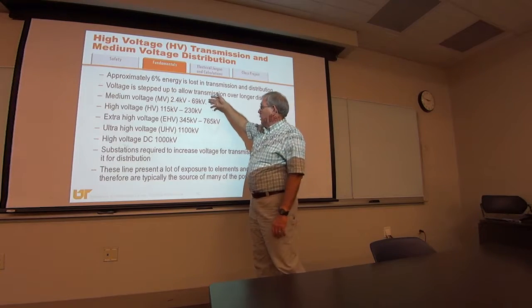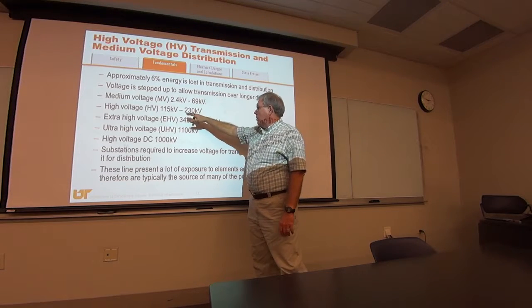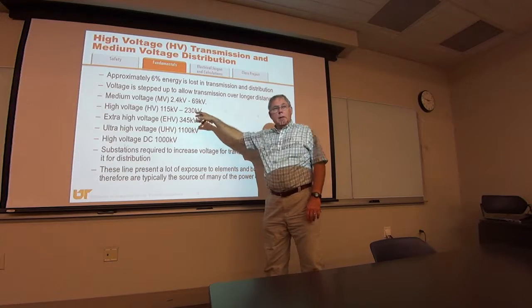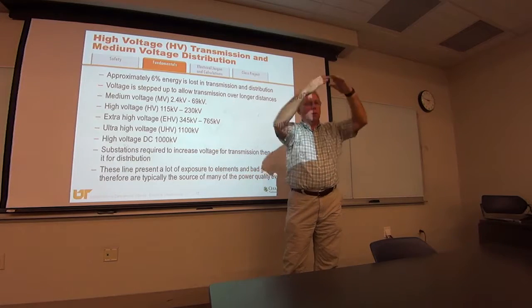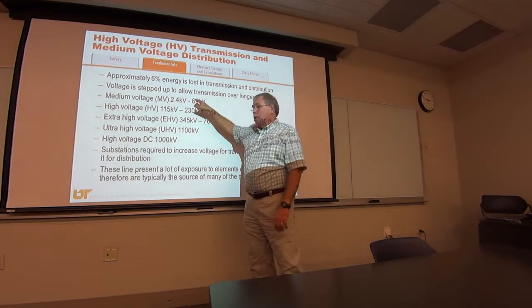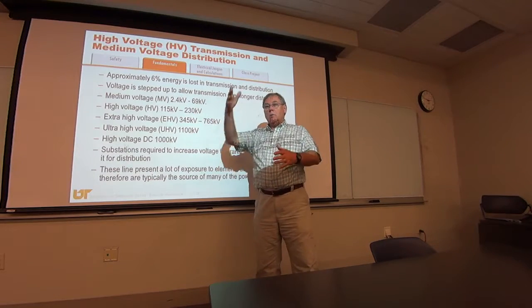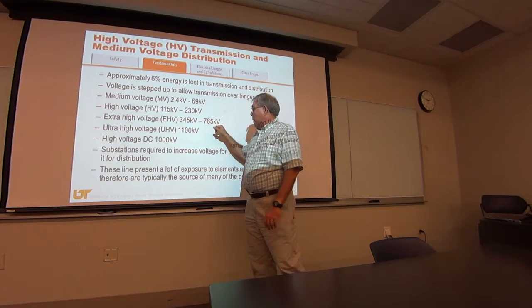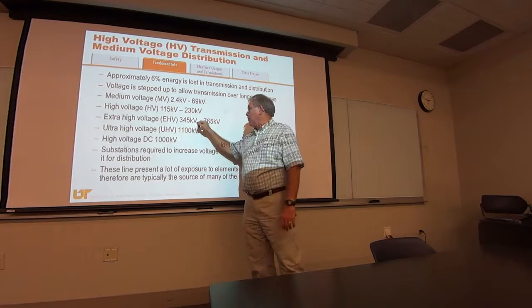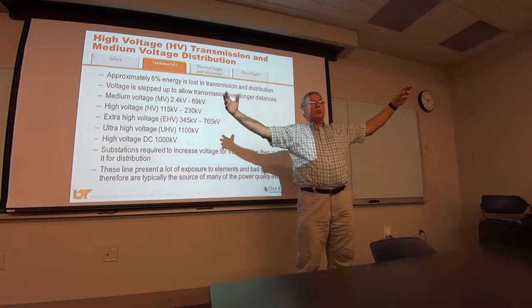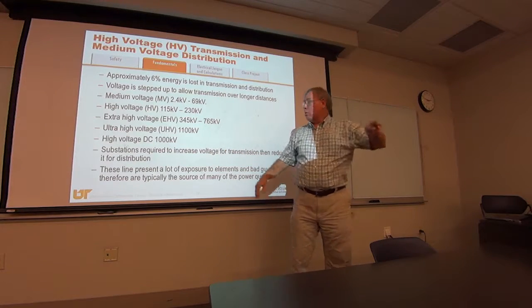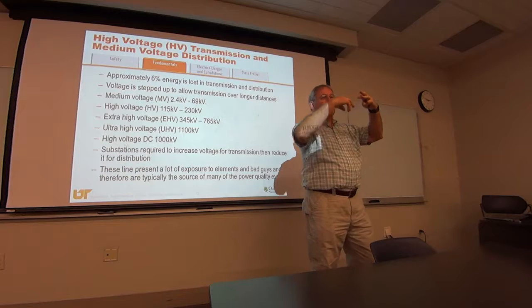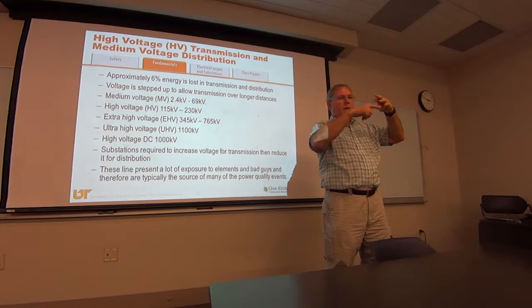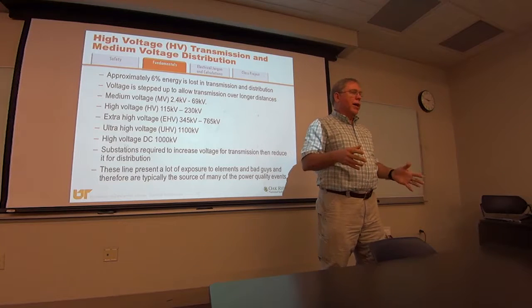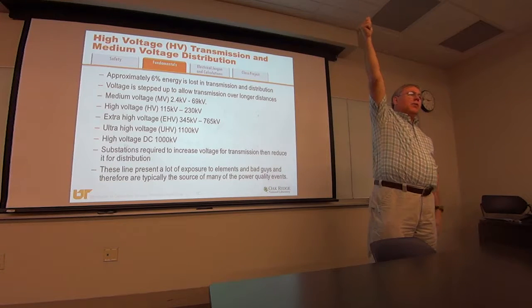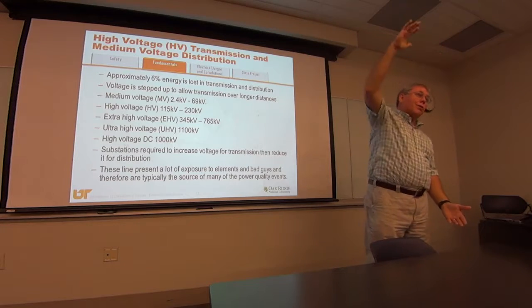And there are different levels. There's medium voltage, 2.4 kV to 69. High voltage is 115 to 230. Most of the TVA lines you see on the big towers are 161,000 volt lines, okay? Some of them are 69, some of them are 46. Those will be on the big tall poles all by themselves. And if you see the big towers, the big wide ones with the three wires on them, those are about 500 kV. And the reason they use three wires is to prevent the corona discharge from getting real bad. If they had one wire there, it would really go bad. You can actually stand under those with a fluorescent light and hold it up and the light comes on. The electric field from that wire to the ground is so great.